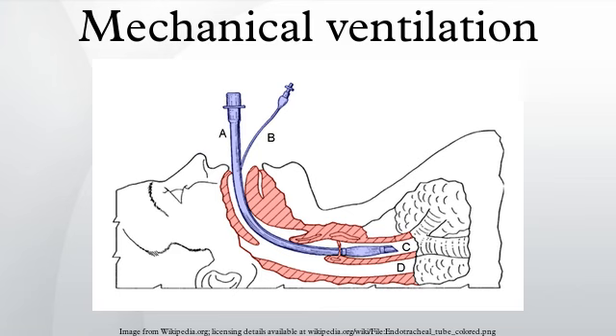Limit. Limit is how the breath is controlled. Breaths may be limited to a set maximum circuit pressure or a set maximum flow. Breath exhalation. Exhalation in mechanical ventilation is almost always completely passive. The ventilator's expiratory valve is opened, and expiratory flow is allowed until the baseline pressure is reached. Expiratory flow is determined by patient factors such as compliance and resistance.